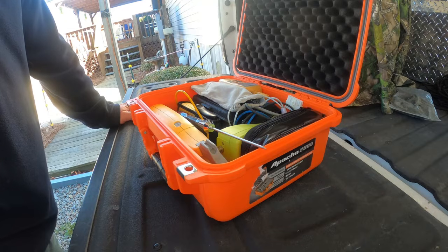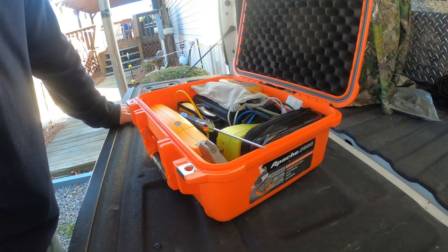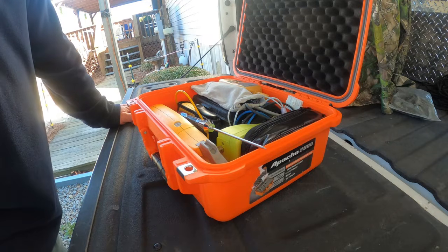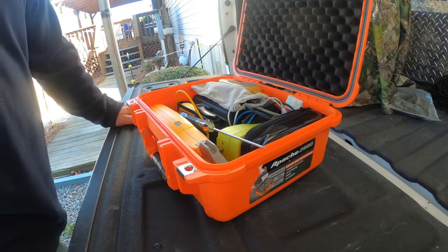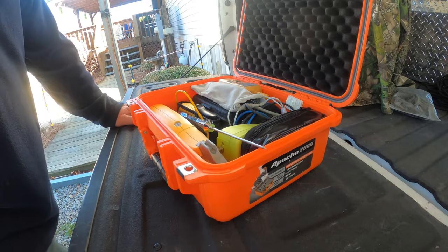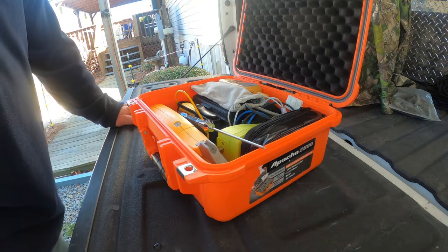You've got your X13 motors. Both of those are more of a constant torque type motor. ECM, we'll say X13. X13 motors are not variable speed motors. They can be installed in a system that maybe has a control board or something along those lines that will energize a different speed in a different mode, but they're not variable speed motors.